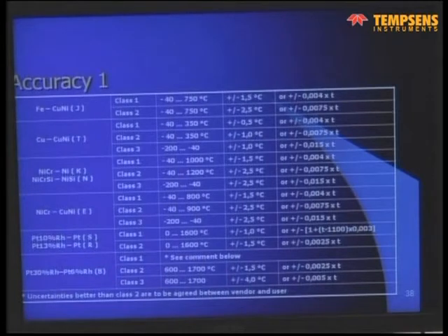Class 3 is mainly for negative temperature. Yes, yes. For example, for type K and type N, it is only for the range from -200. There is a mistake. It must mention -40. Only in that range class 3 is defined. And above -40, it must not comply with class 1 or 2. Mostly it is outside.